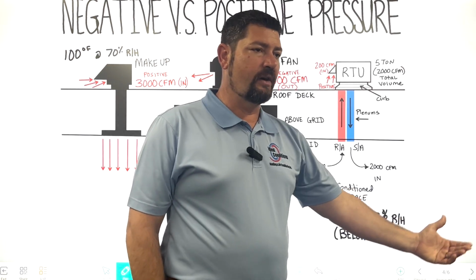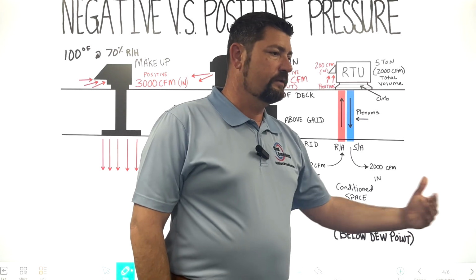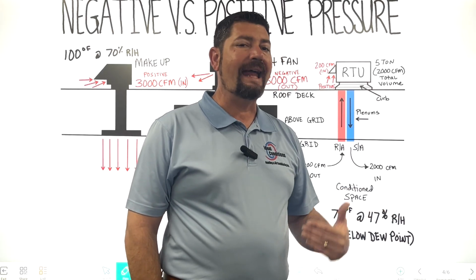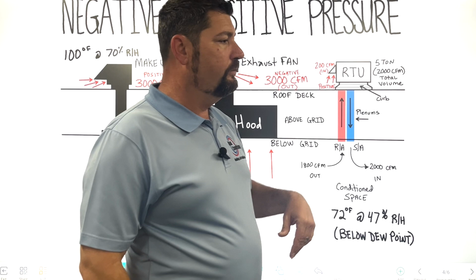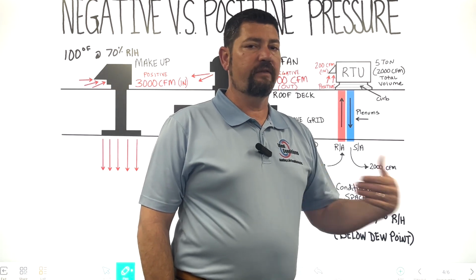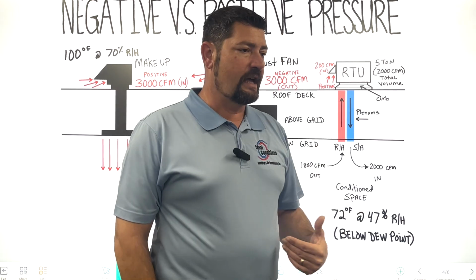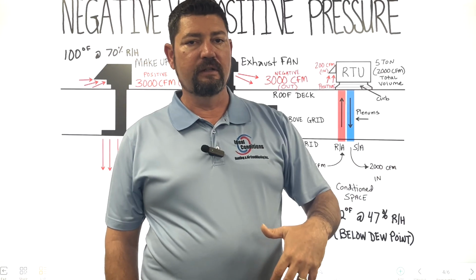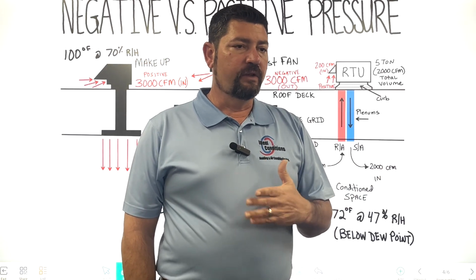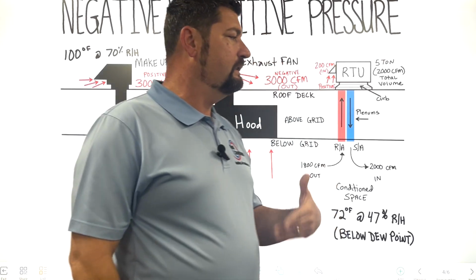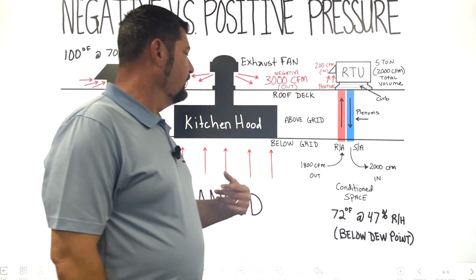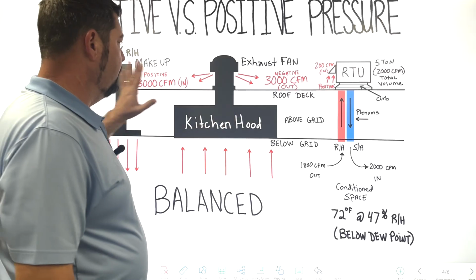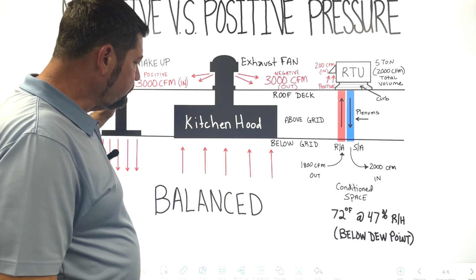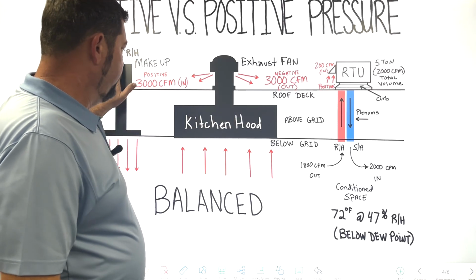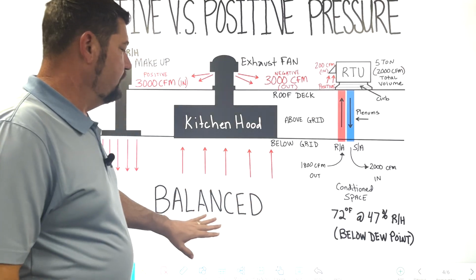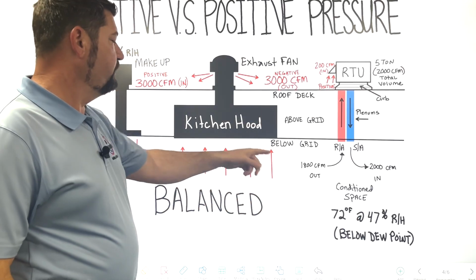I may not have a sweating issue, but now I invited heat through negative pressure, and then I'm going to be having a hard time combating that heat because my RTUs aren't large enough to transfer that heat out of there. These RTUs are sized for the space and how many people are going to be there, and you don't really typically need more BTUs to transfer heat out of the place if you have proper makeup and exhaust, if it's a restaurant, because if this is off, then yeah, you're going to suck all your nice conditioned air right on out of here. These arrows might as well be blue at that point.